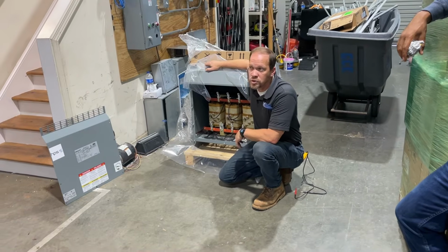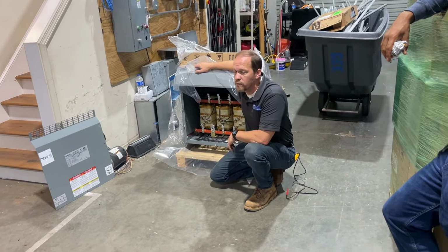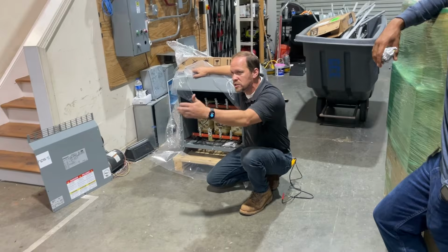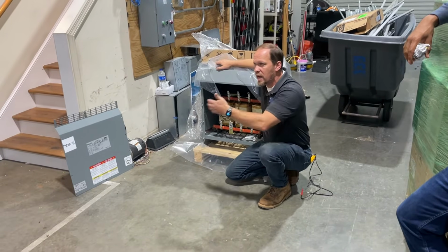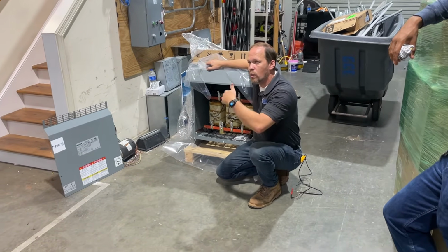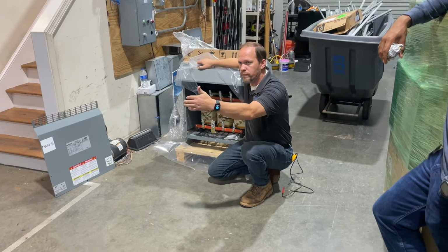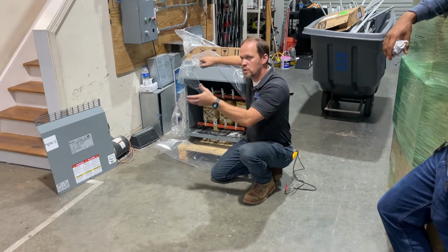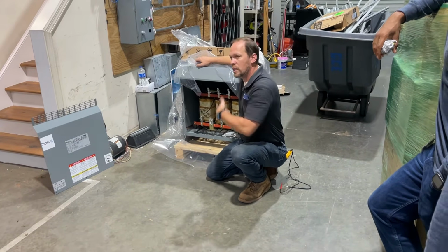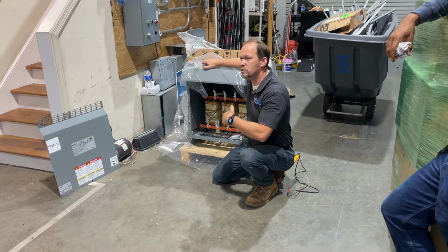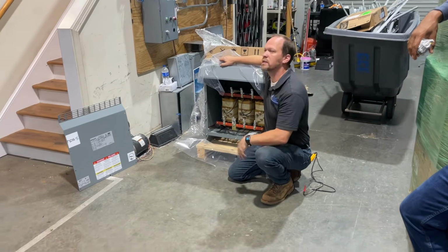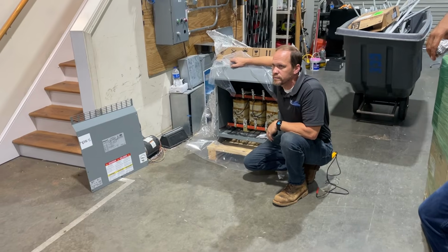But at my house, I did exactly that. I reversed the transformer. I have such a long distance going from where the pole comes in, I installed 2 transformers, one of them with a 240, 480, so I reversed it and then brought it to the transformer at my house and brought it from 480 back down to 240, single phase.